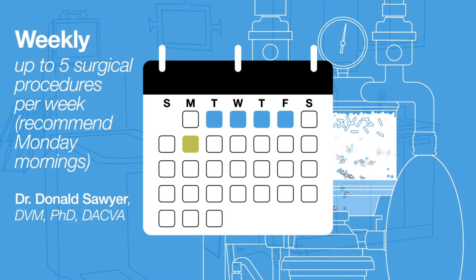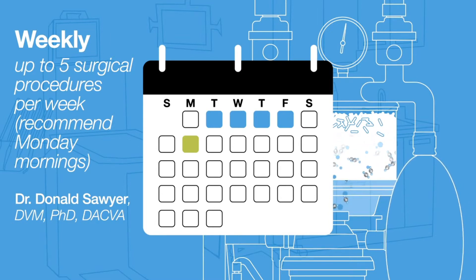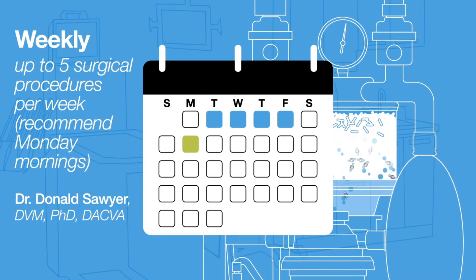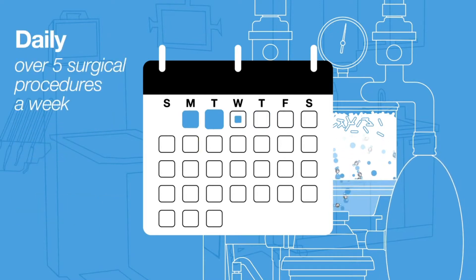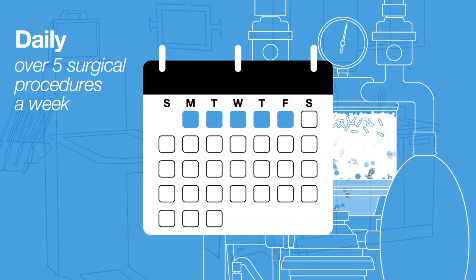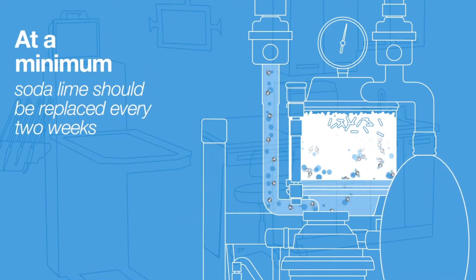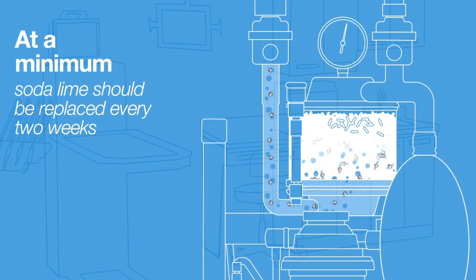Per Dr. Donald Sawyer, founder of the American College of Veterinary Anesthesiologists, a good practice is to discard and replace absorbent after a period of 3 to 5 days. For more than 5 surgeries a week, or if you have a large percentage of dogs over 80 pounds, you may need to change your absorbent as often as every day. At the absolute minimum, your soda lime should be replaced every 2 weeks even if it is not used, for safety reasons.